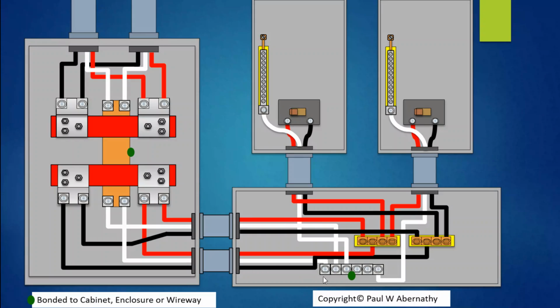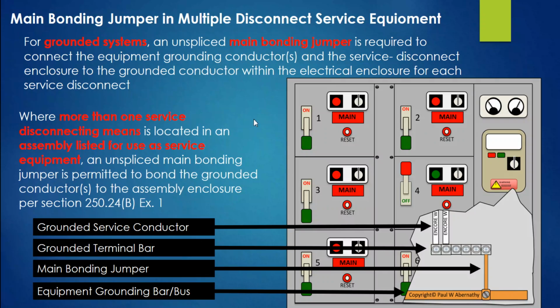Of course, they could be here as well, coming from here. The code allows for that. But anyway, that's the general purpose here, to make that connection where the service disconnecting means is. However, you do have an allowance here where you have an assembly that's listed as service equipment. So this operates under the 6 disconnect rule, and this piece of equipment could be a switchgear.